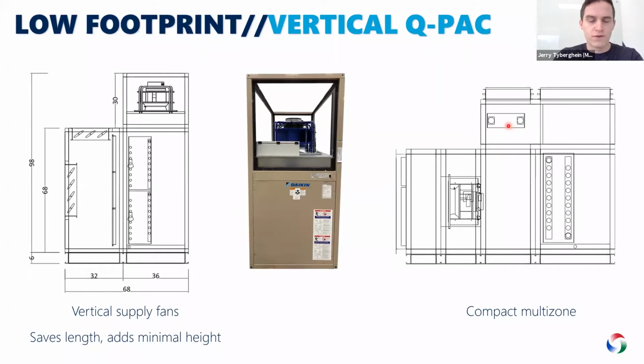So to start, one of our simplest modifications is a low footprint unit using vertical supply fans. So you can see this unit on the left. Maybe you have a mechanical room that's short on length. We can take a fan, rotate it 90 degrees and put it on top. So you now have an upblast fan. It's not rocket science, but in older days where you're using DWDI fans or maybe still using direct drive plenum fans, that could go up to about 60 inches tall on that top deck. So we're only at about 2 to 3 feet, adding these vertical ECM fans on top. So that saves length and adds a little bit of height.